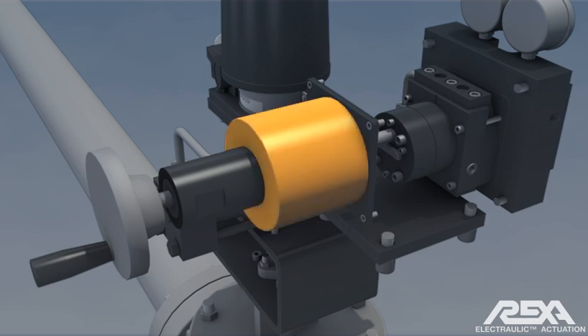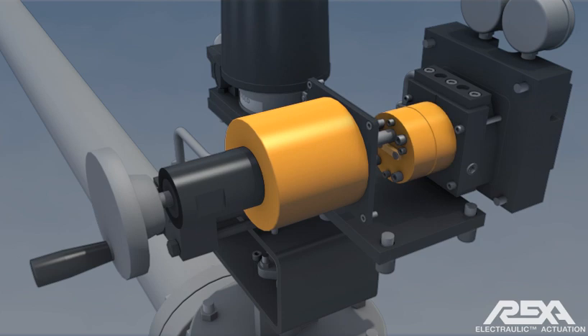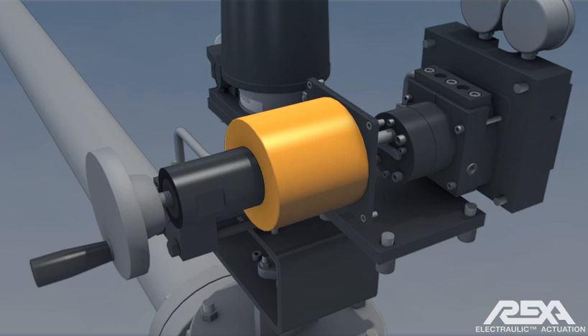The pump motor is a 100% duty reversible unit which drives the internal hydraulic pump. The motor is either stepper or servo. These motors are used because their speed and direction can be precisely adjusted by the position control module to meet the performance required. The motor only activates when a valve position change is required, making it highly efficient.